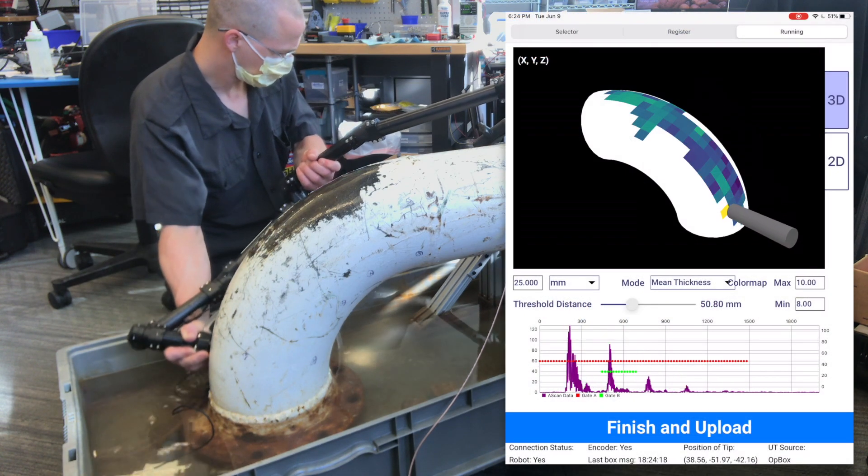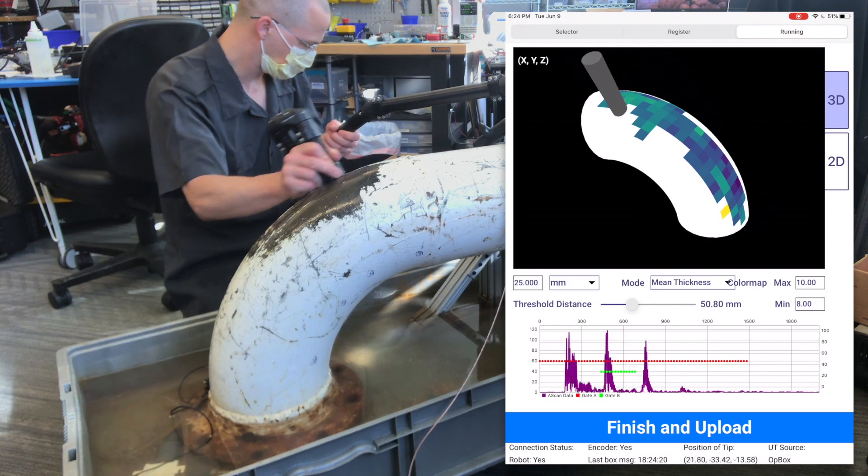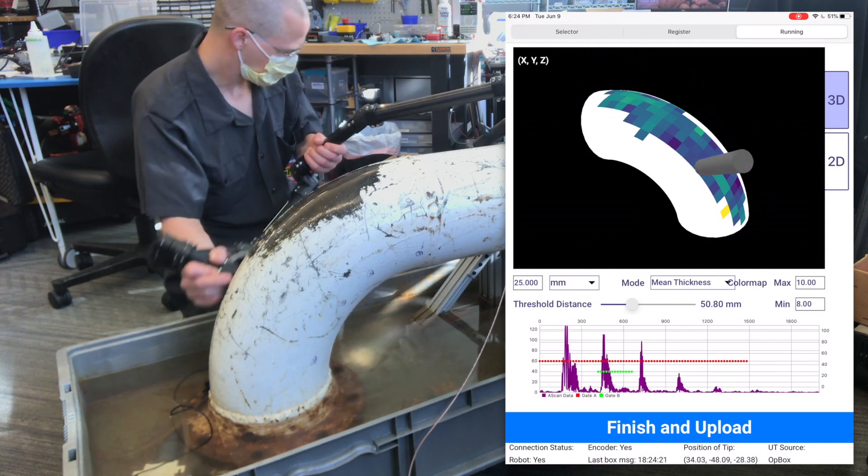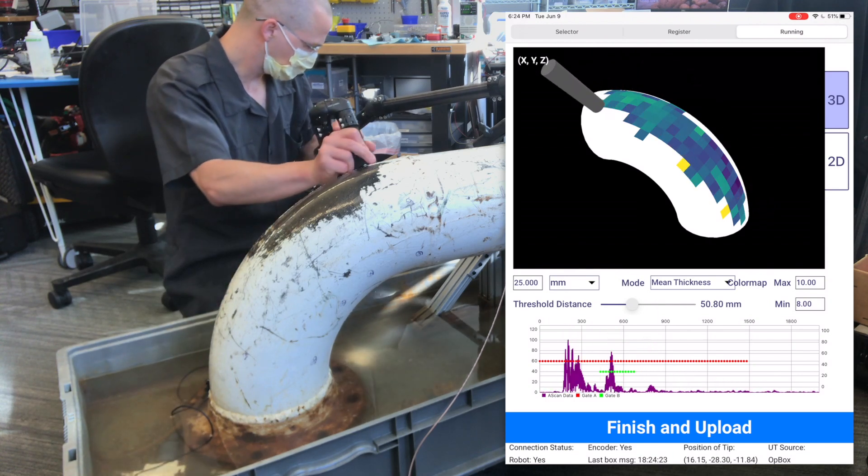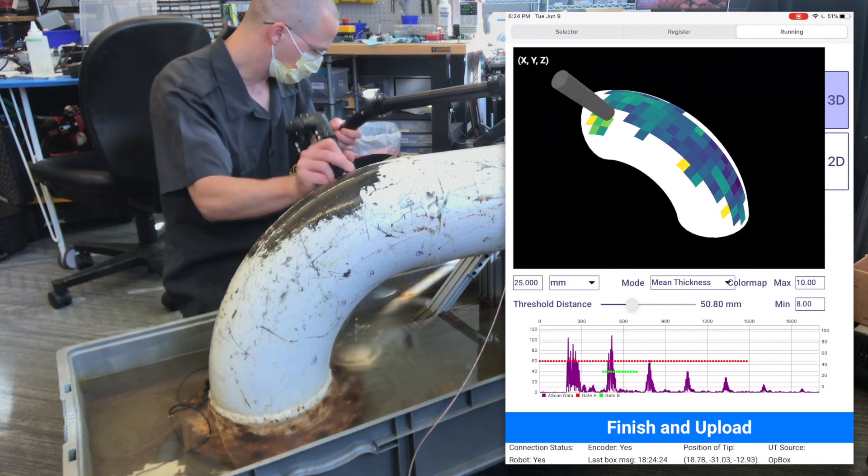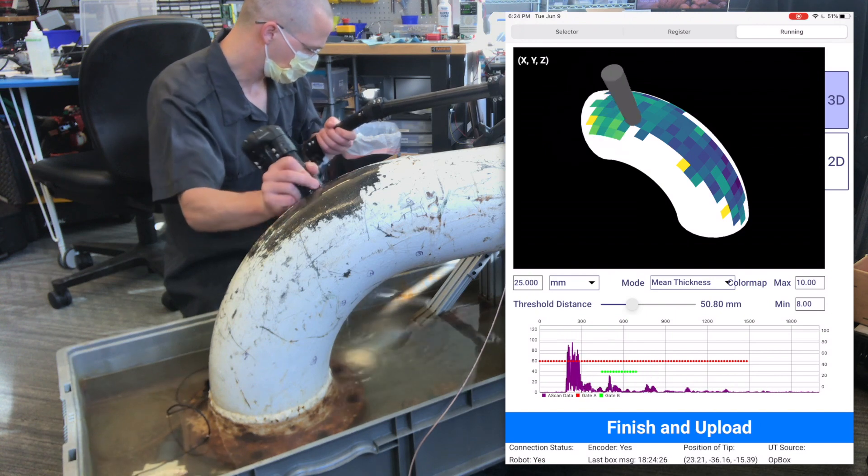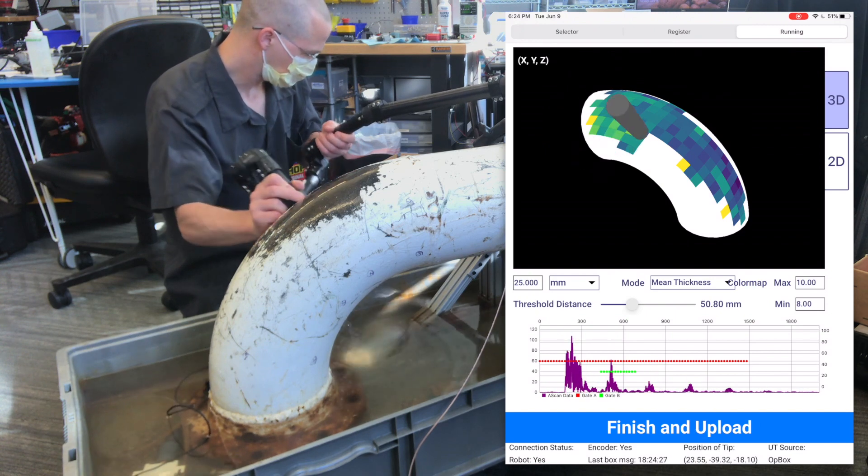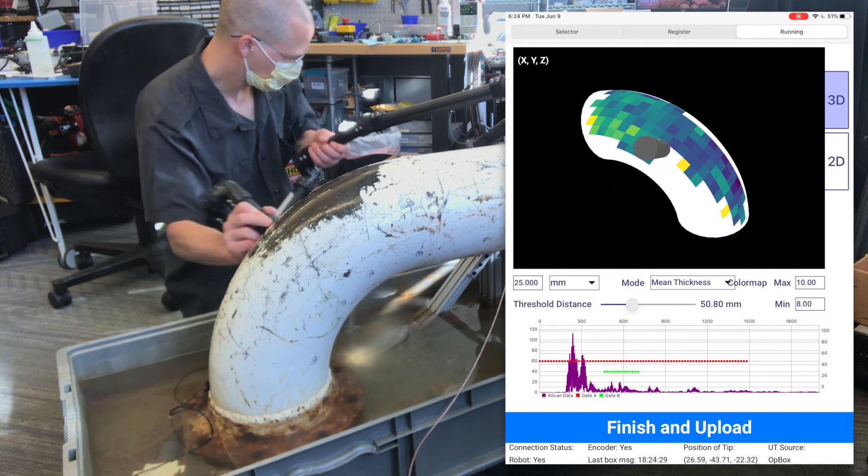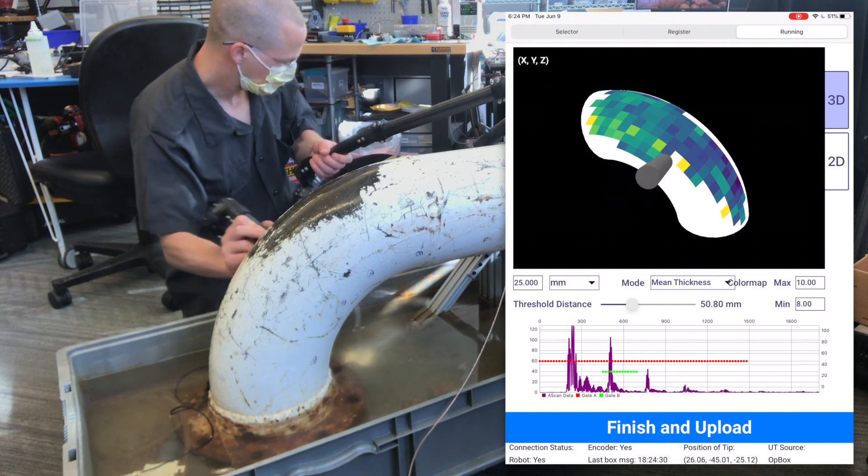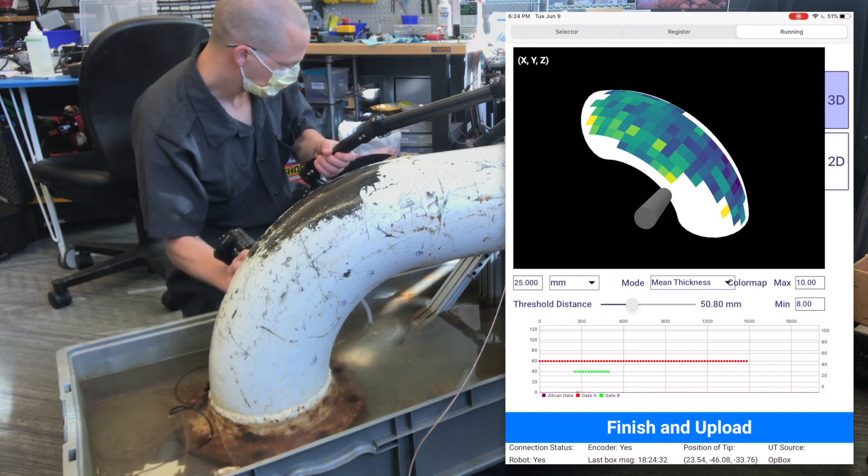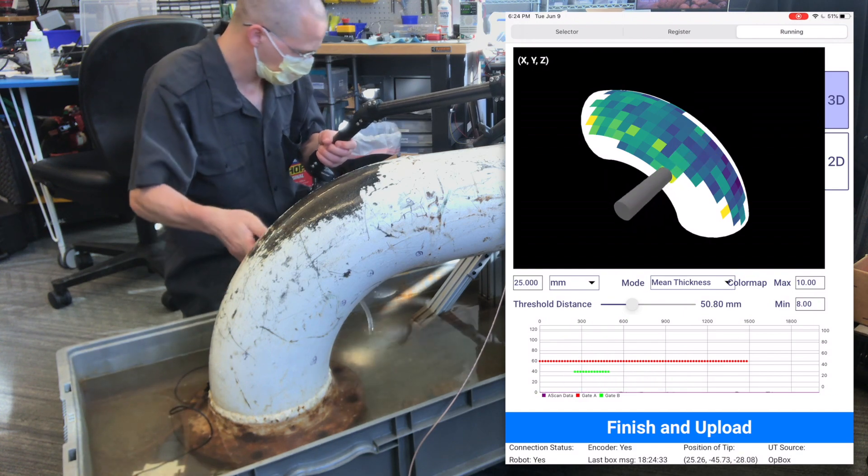As you scan, MAPS measures the full position and orientation of the probe, and uses this information to fill in a 2D gridded C-scan that's mapped onto the actual 3D geometry. With our initial system, we're focusing on UT inspection, but this process can be used with anything that measures surface thickness.